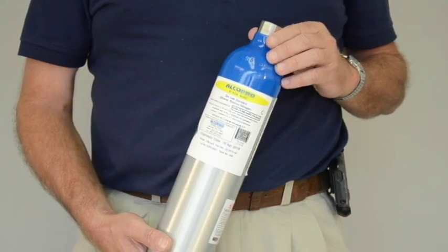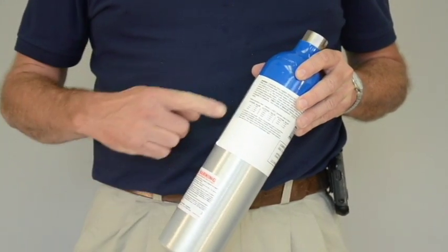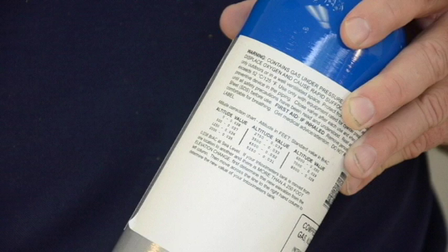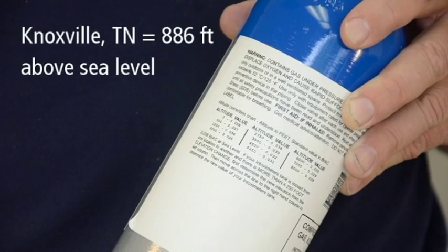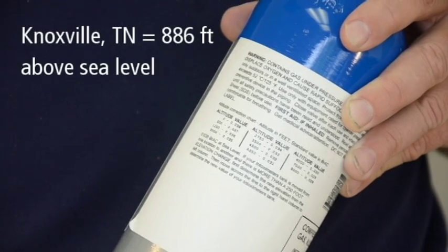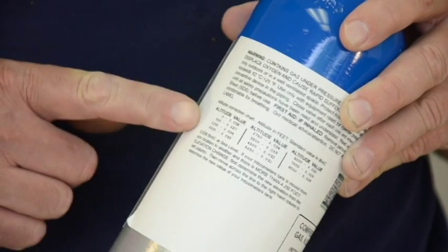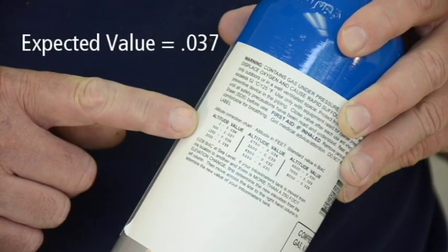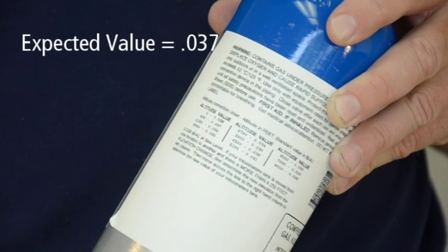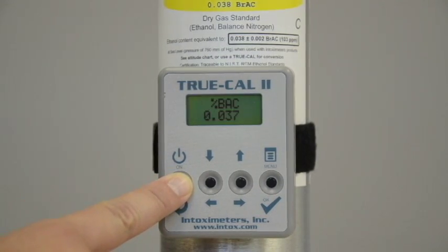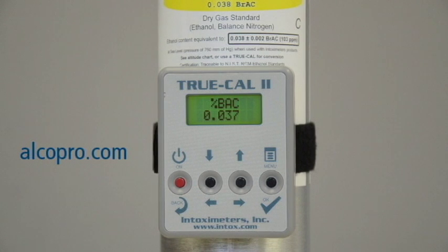The expected or target value of your gas standard can be derived by referencing the altitude chart on the back of your tank. For example, if you are performing a calibration in Knoxville, Tennessee, which has an altitude of 886 feet above sea level, the altitude chart shows the expected value of the alcohol gas tank to be 0.037. You can also derive the expected value of the alcohol gas tank by using a TRUE-CAL device, which uses atmospheric pressure to predict the expected value of the gas. You can purchase a TRUE-CAL device at alcopro.com. Now that you know your expected gas value, you can proceed with the calibration adjustment.